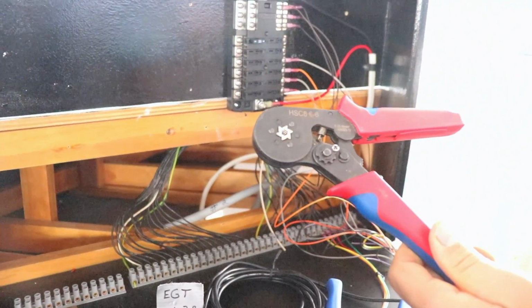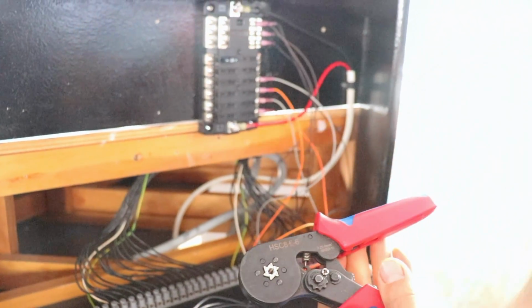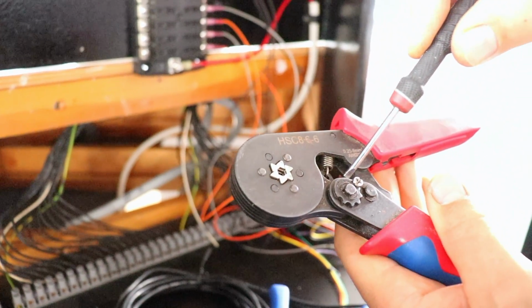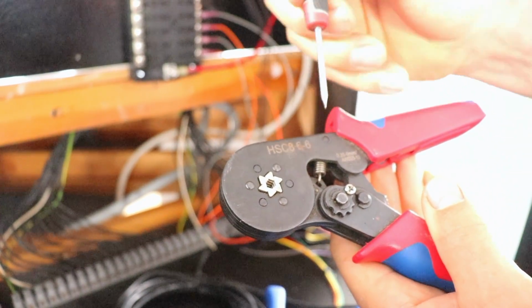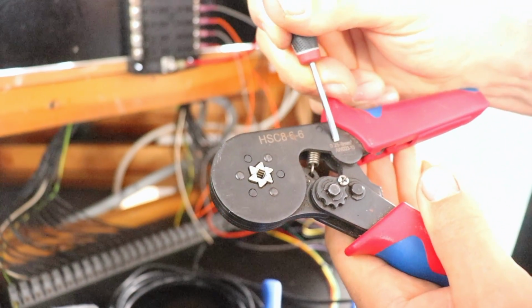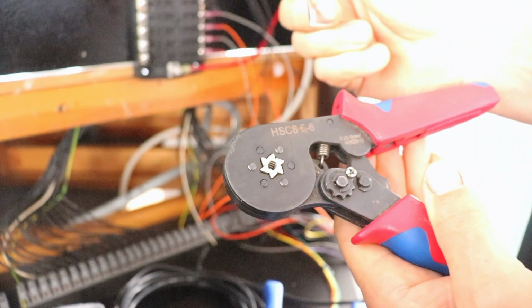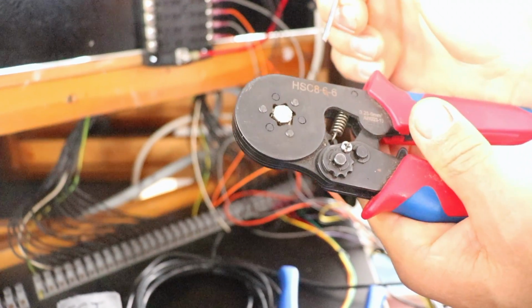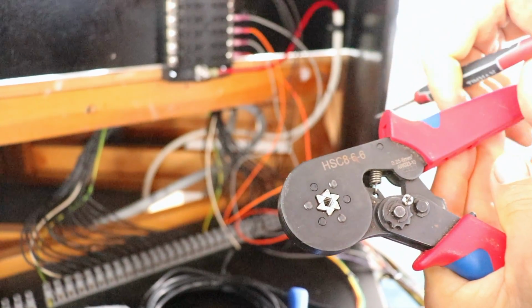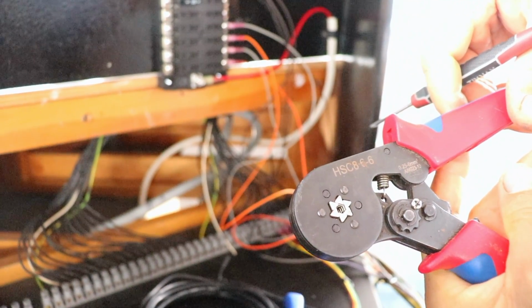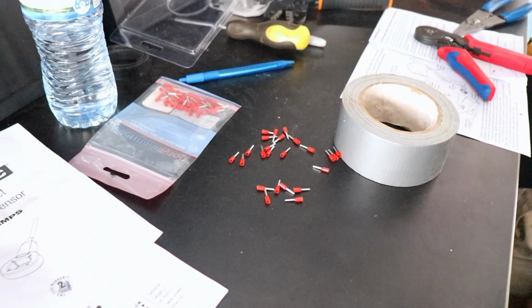This crimper is what we use, and it has a little adjustment cog just down here that goes from 1mm up to 6mm. It wasn't set tight enough to squash the jaws together. There we go, so that's what it does - it basically crushes that central jaw together. So when I did the bootlace lugs, they weren't crimping tight enough, and some of them are failing.